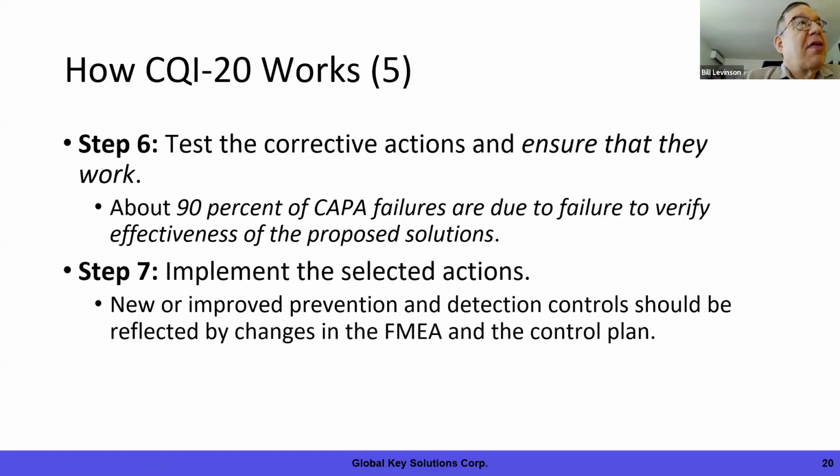Test the corrective actions and make sure they work. And most CAPA failures are due to failure to verify effectiveness of the proposed solution. And this failure to verify shows up very frequently in FDA warning letters as well. So you have to make sure the proposed solution works.